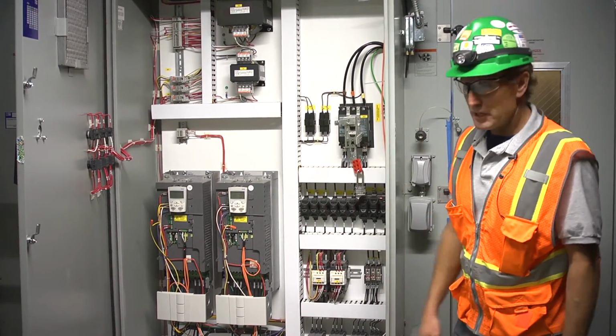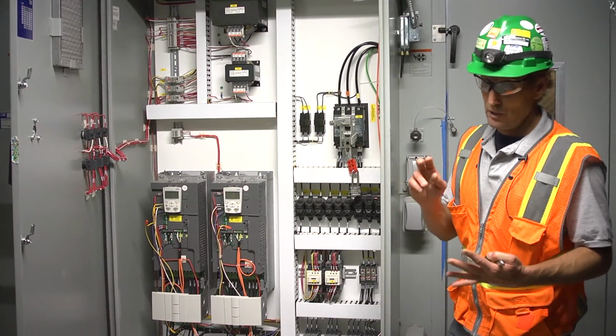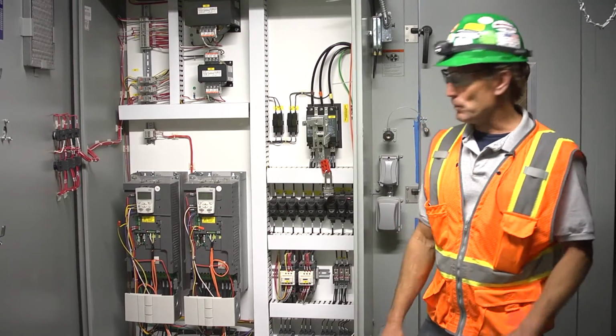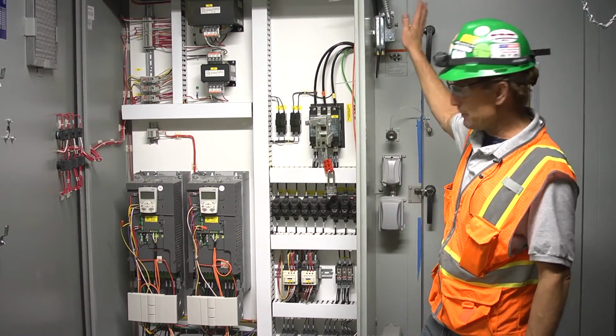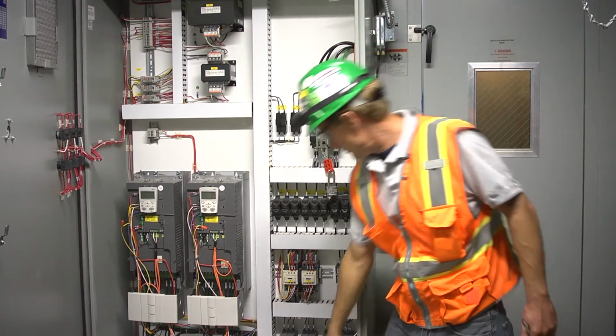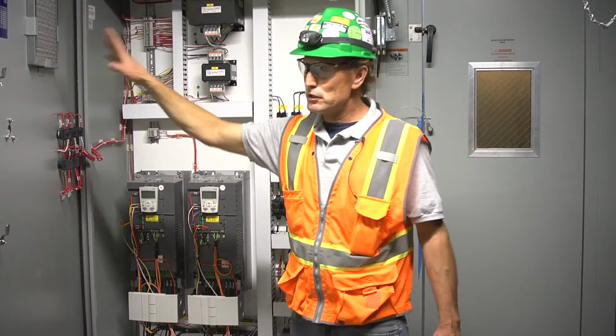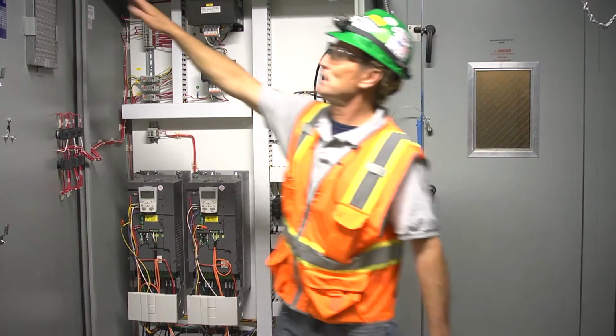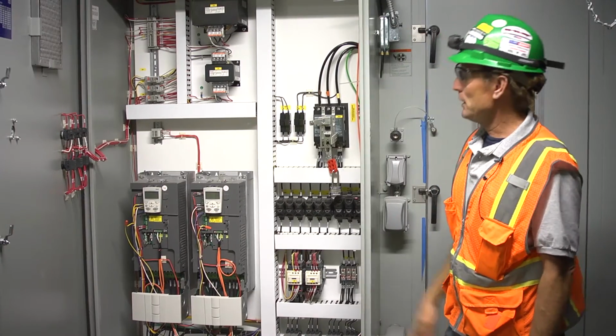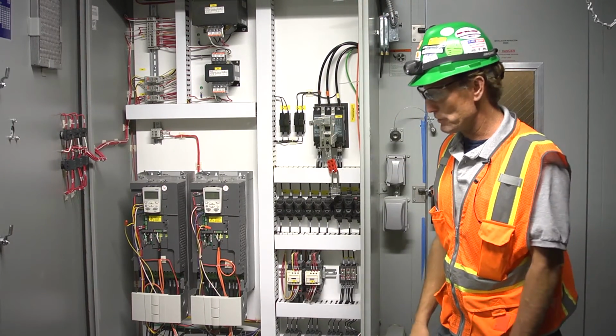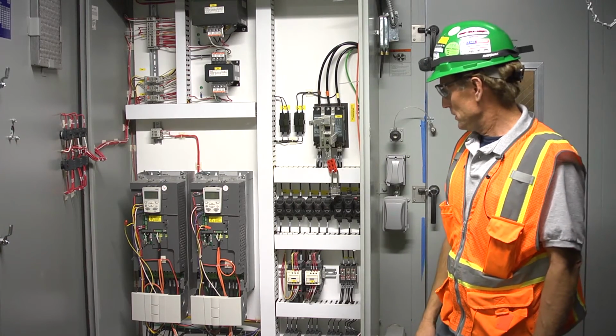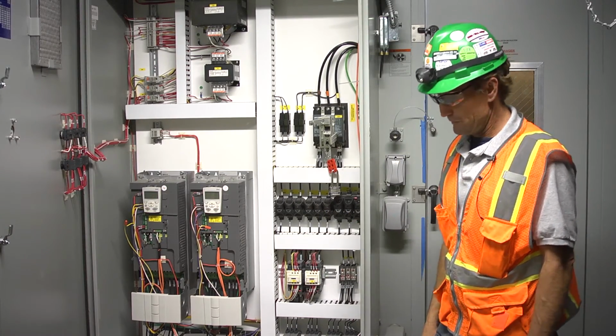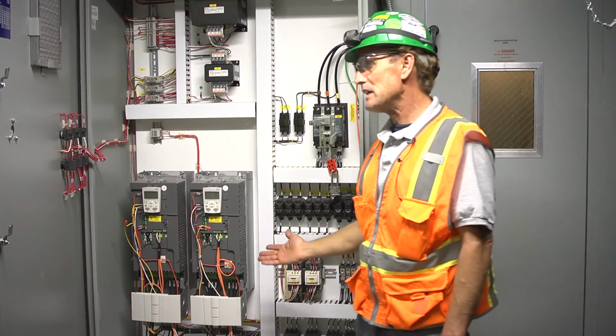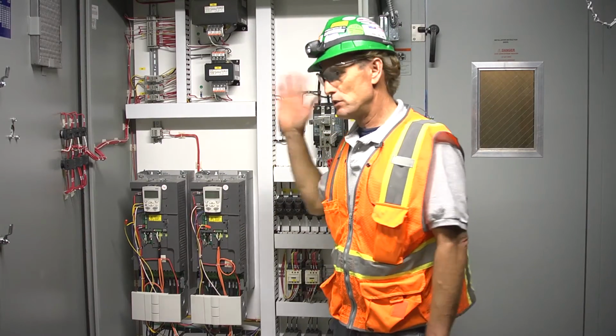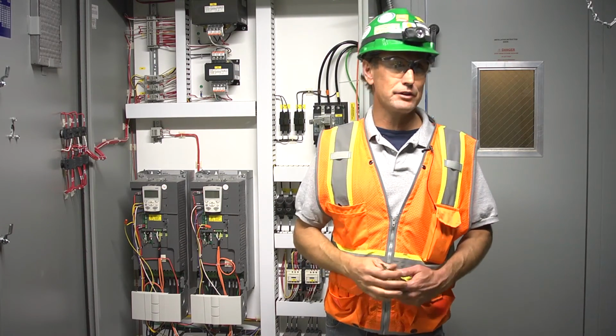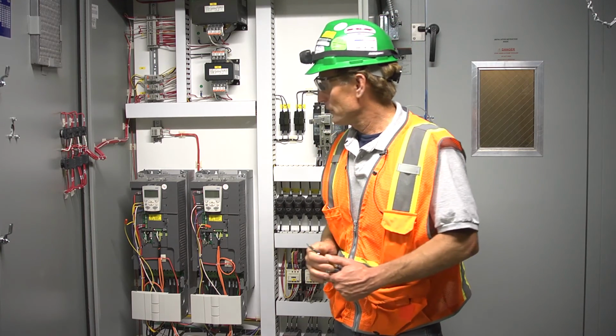Maintenance-wise, any electronic components are usually susceptible to moisture, vibration, and dirt. So we try to be aware of any vibration coming from the unit, and any dirt being brought in through here or through here. Just keep dirt and dust out of the unit, keep the door seals clean and functioning. And then of course moisture, any moisture coming from the piping or roof or whatever should be kept out of the unit. And there should be no issues with that. After the first year, the only other maintenance thing involved with the cabinet would be to secure the unit, and go through and tighten all the electrical and check for heat or vibration or any kind of high current conditions.